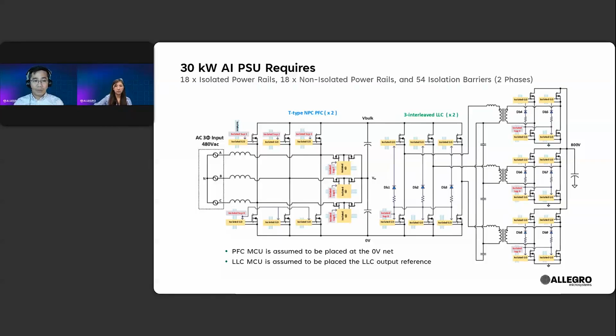However, this solution is limited to certain applications that need to allow initialization during startup, applications that have no extreme duty ratio, and applications that don't need negative supply, just like, for example, a PFC. So the LLC stage requires in general only 2 isolated bias rails and 9 non-isolated bias rails. You may notice in the schematic that we are only running one phase, handling around 15 kilowatts. For the complete system, we need to double the number of gate drivers, bias supplies, and isolation barriers.